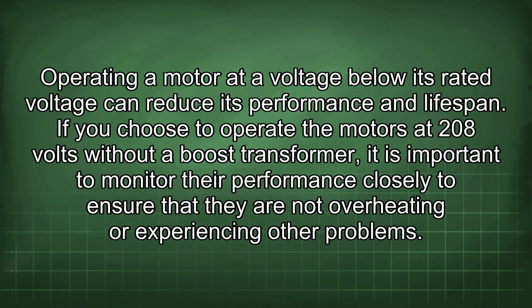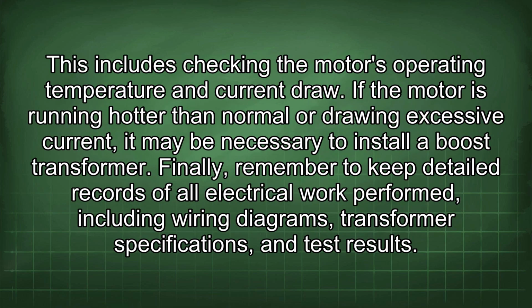If you choose to operate the motors at 208 volts without a boost transformer, it is important to monitor their performance closely to ensure that they are not overheating or experiencing other problems. This includes checking the motor's operating temperature and current draw.